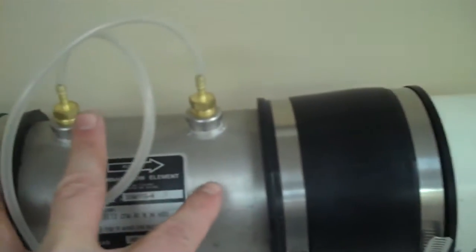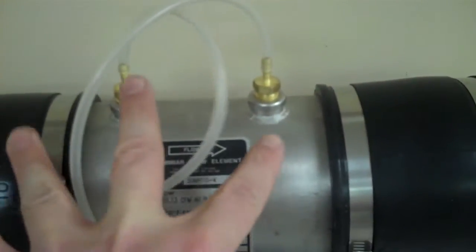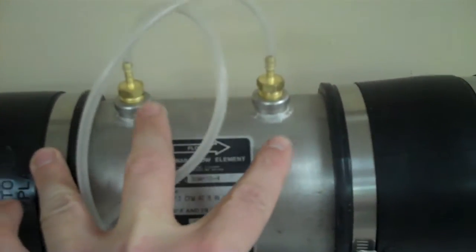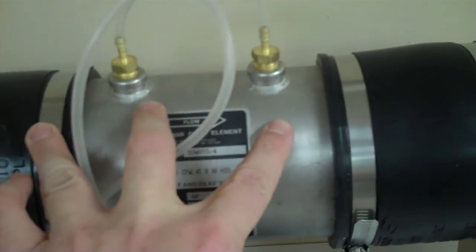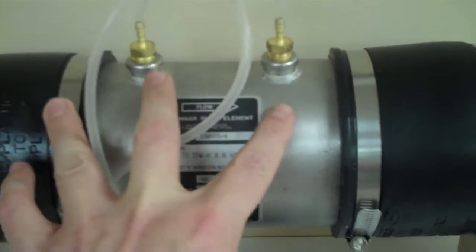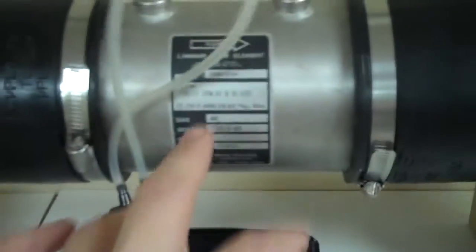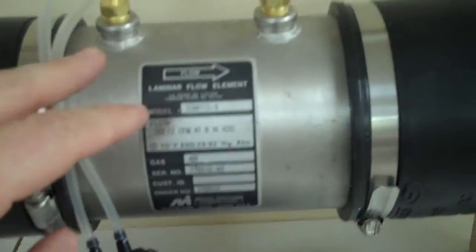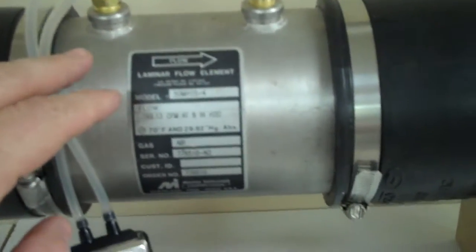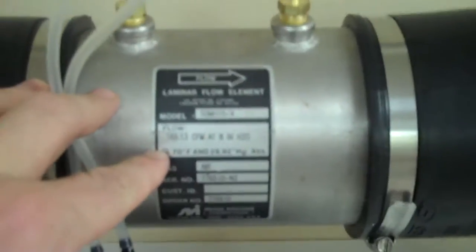Real simple. What it does is it measures the pressure drop against this element. It's a calibrated element, and with the pressure drop, you can actually determine cubic feet per minute flow. So this one here is 169.13 CFM at 8 inches of water, and it's a linear flow.